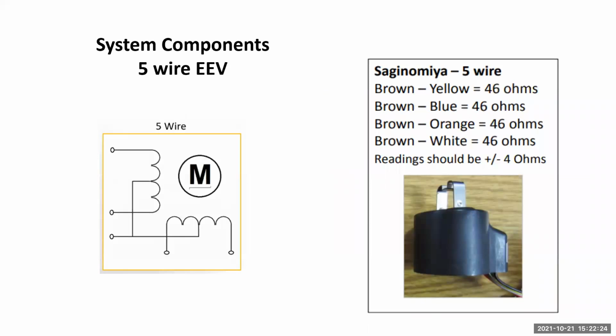If you have a ground, sometimes it can read as 0 volts DC. And here's the 5-wire one. It's the same thing. Just check them out. Make sure we got that good. You also want to be certain that they're seated good on top of the valve. They should spin, but if you can grab a hold of it and lift up, then we know it's loose. Push it back on there till it clicks.